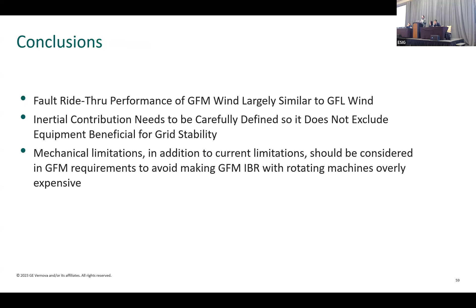The conclusions: fault ride-through performance of grid-forming wind is largely similar to grid-following wind — the performance during the fault is different but which events it can ride through are mostly the same. Inertial contribution needs to be carefully defined so it does not exclude equipment that is actually beneficial for the grid. If we set requirements of 7, 5, 3, or 4 seconds and someone tests in one of the edge cases, they could wrongly disqualify a turbine that is otherwise beneficial. Mechanical limitations in addition to current limitations must be considered, or we run the risk of making grid-forming IBRs overly expensive.